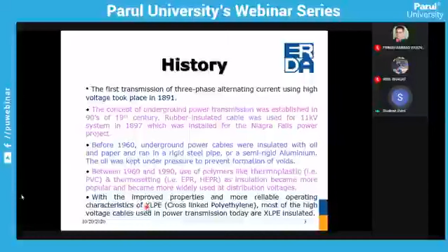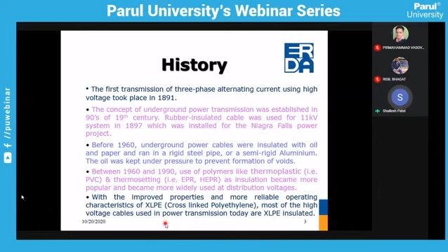It needs to be noted for students that cross-linked polyethylene is widely used across the world because it has good bending capability, because while laying, the cable will undergo bendings. If a cable has no bending characteristics, then the insulation may get damaged during laying itself, and it will not sustain the supplied power. So, good dielectric strength and good bending strength is why it is widely used as the insulating material for underground cables.